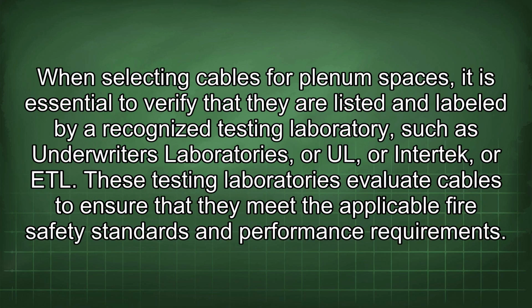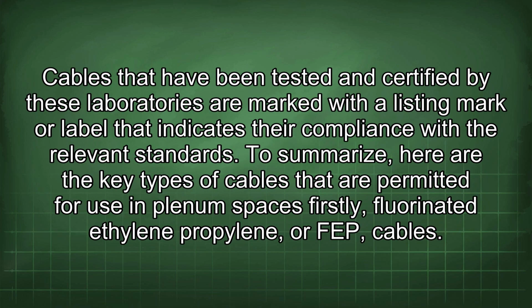When selecting cables for plenum spaces, it is essential to verify that they are listed and labeled by a recognized testing laboratory, such as Underwriters Laboratories, or UL, or Intertek, or ETL. These testing laboratories evaluate cables to ensure that they meet the applicable fire safety standards and performance requirements. Cables that have been tested and certified by these laboratories are marked with a listing mark or label that indicates their compliance with the relevant standards.